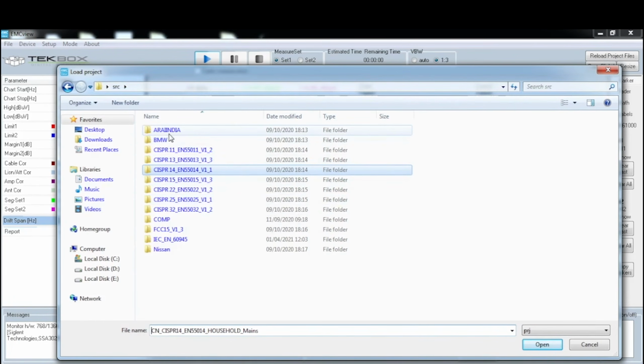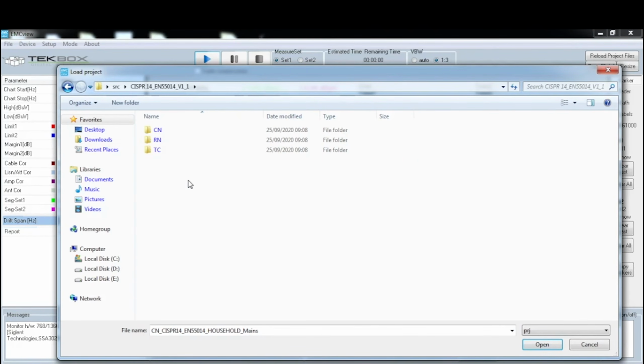As you can see on the screen, you have a wide selection of different testing standards. You have the automotive BMW testing standards, FCC 15, which is the standard they test to in the United States, and you have CISPR 11, 32, all sorts. For this product, I know the proper testing standard that it needs to be tested against is EN 55014. So I'm going to click this one.